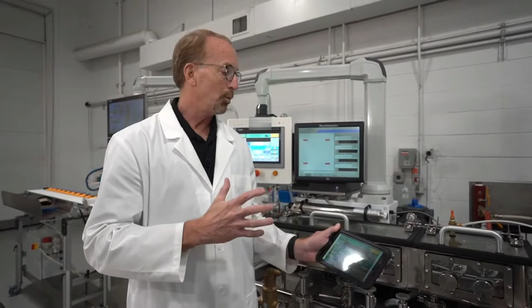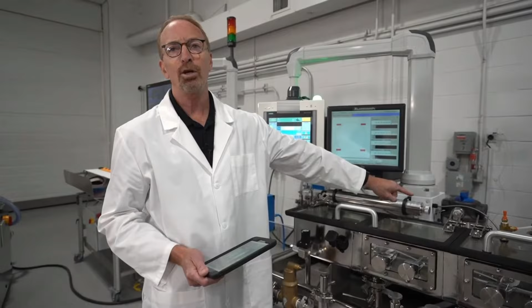Something else you're going to notice here, and filtration is a key item on medical applications. You need to go to minimally a 5 micron. In this case, we're actually going to 0.5 micron filtration, because the better the filtration, the longer the span between necessary flushes. Also there is a UV light. UV light is basically like a black light. It renders the germs sanitary, so they can no longer reproduce. They just die, become pyrogens, and the filter then filters those dead germ bodies out, the pyrogens.